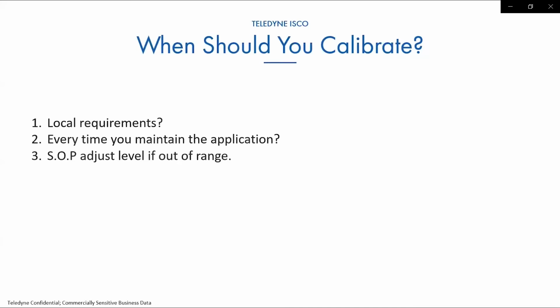Should you calibrate every time you go out and maintain the application, like checking for debris and stuff? It's probably a good idea to verify your calibration and not necessarily adjust it. Depending on your standard operating procedure, if you measure your water depth and you're within 1/4 of an inch, and your requirements may be a little bit different, you might not necessarily need to do the calibration. What I found is that some people go out there and calibrate every single time, and then they keep adjusting it up and down, and what you end up doing is just chasing the calibration. Left alone, you would probably have more accurate readings. So just check with your local requirements to see how often you need to calibrate.